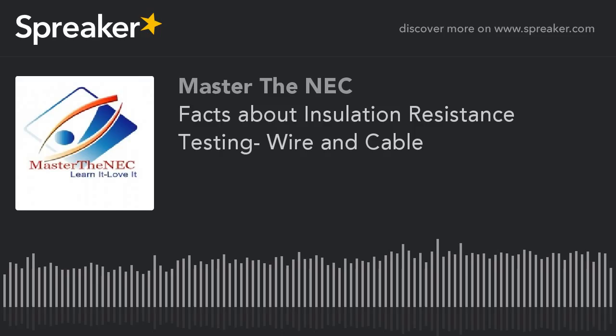Now, what about a metal clad cable? Well, a lot of people want to do these megohm tests on that, and if all the insulated conductors are in good shape, the readings can vary, because when you go from insulated conductor to insulated conductor, if I don't see something that totally plummets down into the very low kilohms, if I get anything in the megohm range, then I've got to first of all say, look, I'll investigate it, but that's not unheard of, because these are two insulated components, okay?